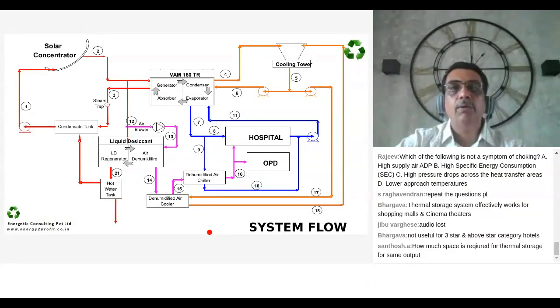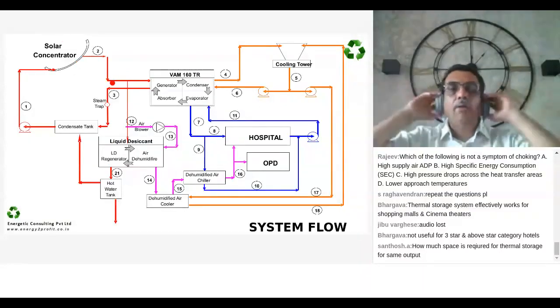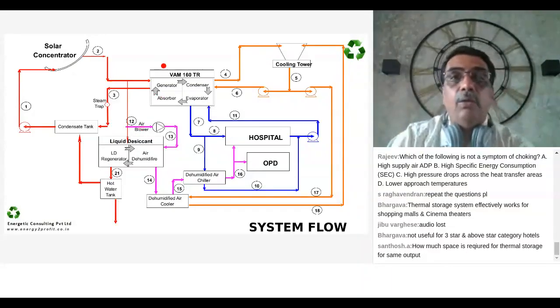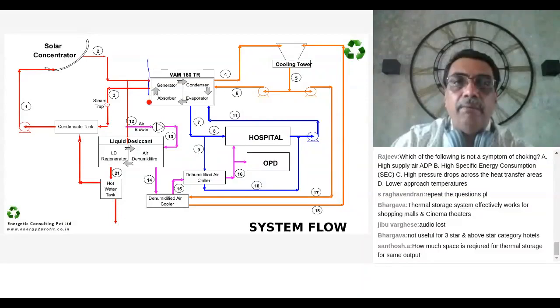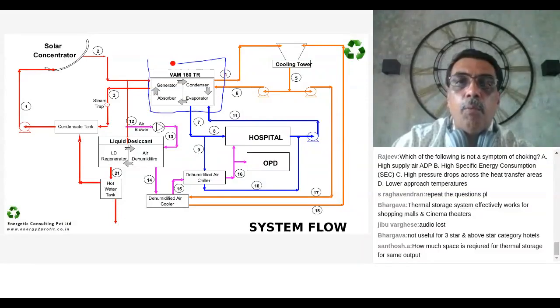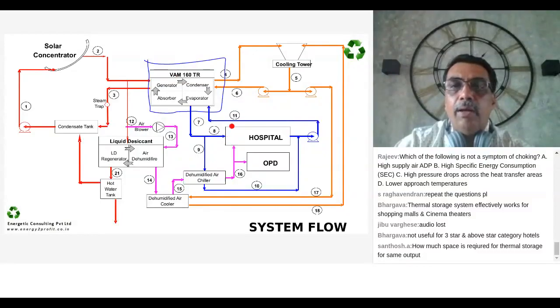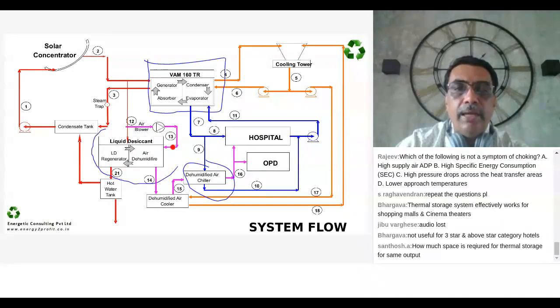I'll show you the liquid desiccant separately. The whole system looks like this. Solar concentrator generated steam. Out of the steam, some part was given to the VAM, vapor absorption machine, which provided chilled water for the hospital conditioning. This was the liquid desiccant dehumidification, and the dehumidified air was given for the OPD. The liquid desiccant system, which is shown here, provided dehumidified air for the hospital and OPD together.